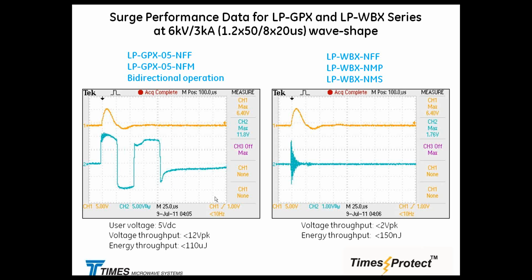This is for the GPS protector. Here is one which goes from 2 to 6 gigahertz. GPS has to make provision for a 5 volt bias voltage to power it up. That's why you see the protection level of 12 volts, factoring in that 5, 6 volts. If you are doing a high bandpass filter protector, you don't have the DC bias at all. So if you shoot 3,000 amperes, you can limit the voltage to less than 2 volts peak. So there are many different RF protection topologies.